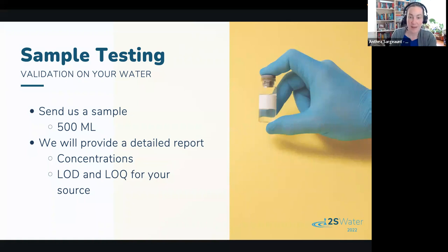On the data format from our unit: the path of the data is we generate raw spectral data, send that to the cloud for analysis - our heavy analytical engine is up there. It converts that data about light into data about metals, and then we deliver that data as a parts per million or parts per billion number to the operator. We then do control system integration on a case-by-case basis, dealing with the control system you have. That's something we're happy to customize based on specific clients, or we can move internally or entirely outside your system, if that makes sense.